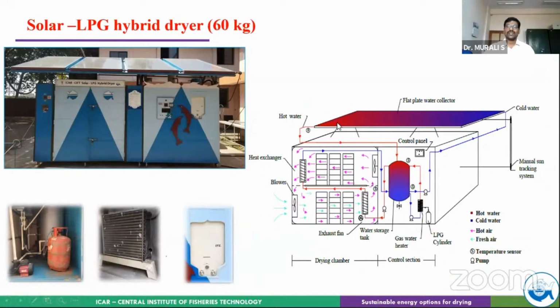There is a temperature sensor at the top and another at the bottom. It continuously checks the temperature difference between the tank bottom and the collector outlet. We can set this temperature requirement, say about 10 degrees Celsius. If there is a difference of 10 degrees, the pump will run and the water will come. Otherwise it would run continuously and all the water would get mixed up, and we may not have the thermocline system, so cold water would go inside and drying would not occur. That's why we have kept 2 sensors to regulate the pump.